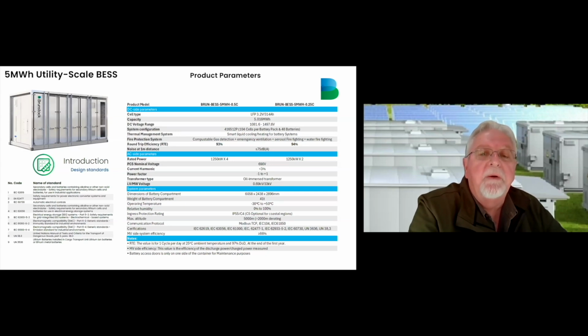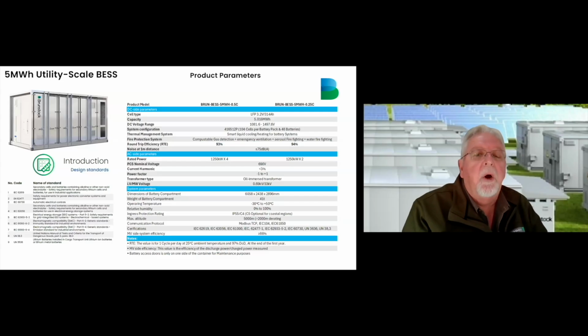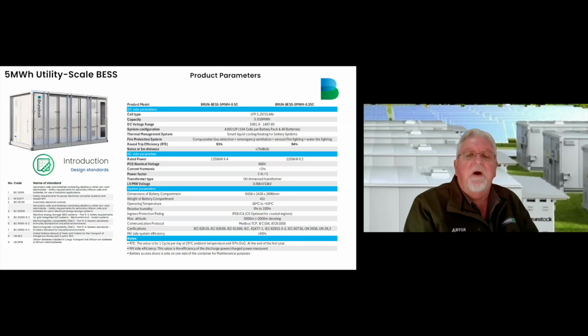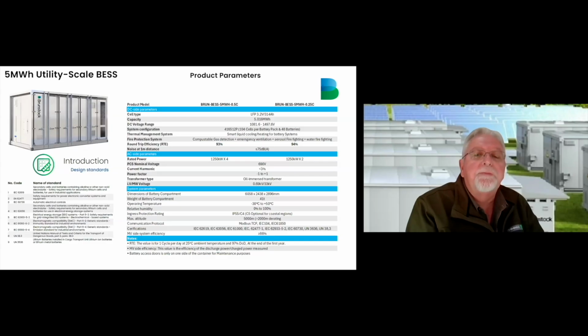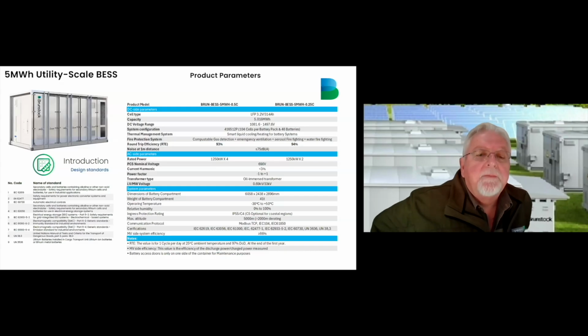It's 20-foot containers, both the 3 megawatt hour and the 5 megawatt hour container. The 5 megawatt hour container weight is 41 tons. Both systems' operating temperature range is minus 30 degrees to plus 50 degrees Celsius. The relative humidity is from 0 to 100%. The ingress protection rating is IP55 C4 as a standard, but C5 is optional for coastal regions. Your maximum altitude is 5,000 meters, but it will start derating above 2,000 meters. We use Modbus protocol to the external devices. It complies with all the international certifications.